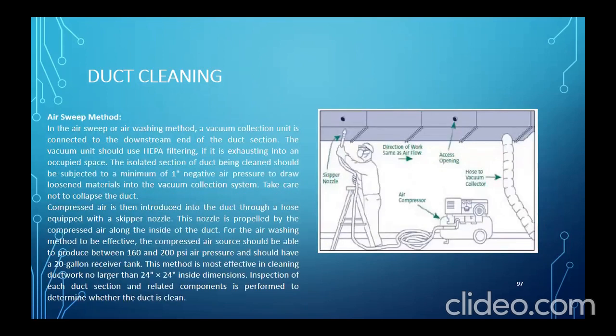So, air sweep method. So, ito, nozzle na. In the air sweep or air washing method, a vacuum collection unit is connected to the downstream end of the duct section. The vacuum unit should use HEPA filtering if it is exhausting into an occupied space. The isolated section of the duct being cleaned should be subjected to a minimum of 1 inch negative air pressure to draw loosened material into the vacuum collection system. Take care not to collapse the duct.